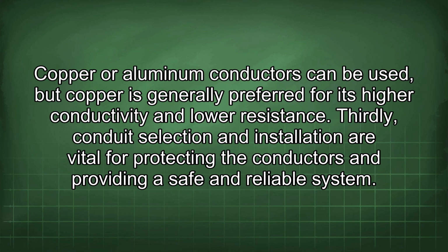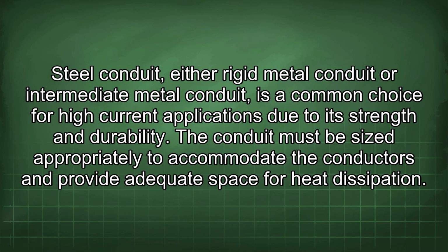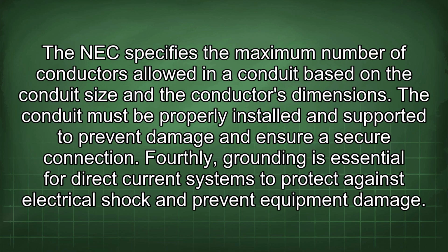Thirdly, conduit selection and installation are vital for protecting the conductors and providing a safe and reliable system. Steel conduit, either rigid metal conduit or intermediate metal conduit, is a common choice for high current applications due to its strength and durability. The conduit must be sized appropriately to accommodate the conductors and provide adequate space for heat dissipation. The NEC specifies the maximum number of conductors allowed in a conduit based on the conduit size and the conductor's dimensions. The conduit must be properly installed and supported to prevent damage and ensure a secure connection.